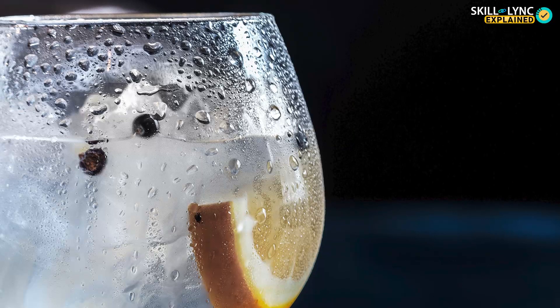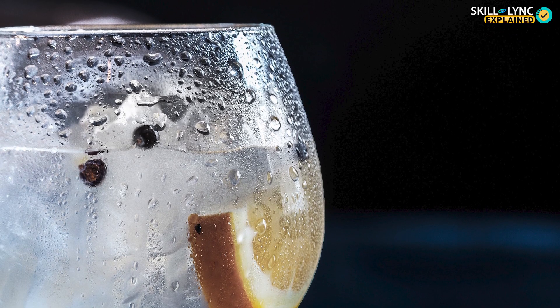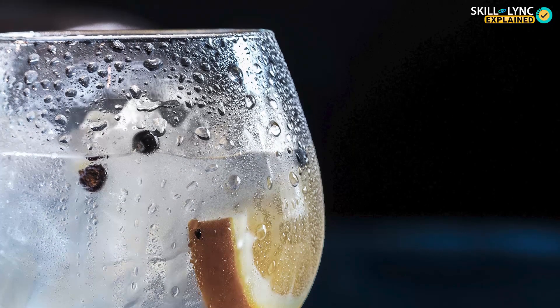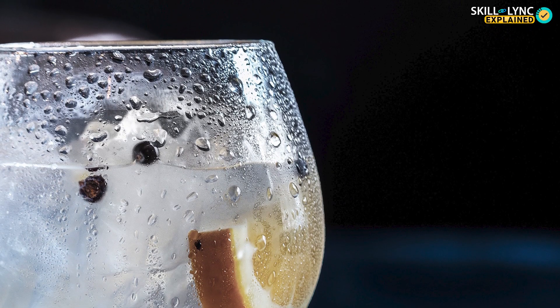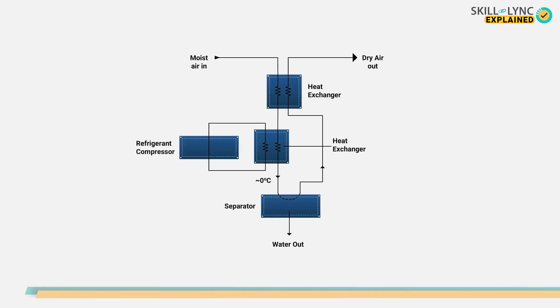As we know, on cooling air, water condenses and the moisture content decreases. This same principle is used in a refrigerated dryer. A refrigerated dryer cools the air to just above 0 degrees Celsius, which causes almost all the water to condense and get collected in a separator.